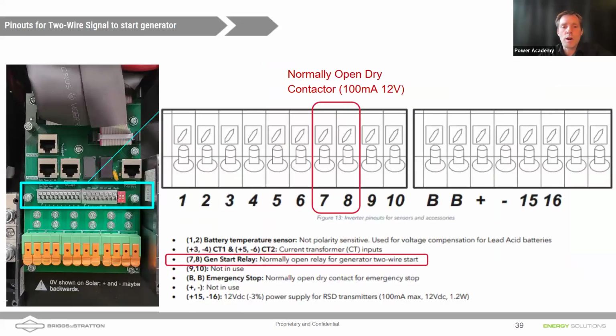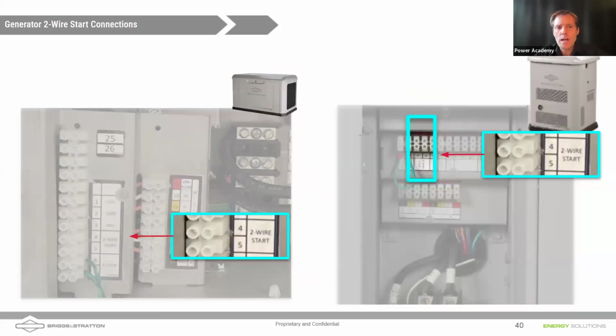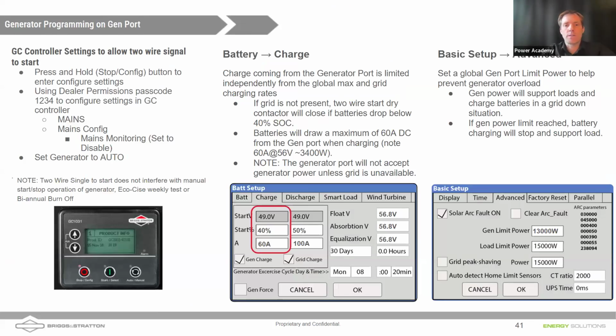You also want to make sure you wire that two-wire signal to start if you have an automatically starting generator. On our generators, that's pins 4 and 5 on our control boards. And that's a normally open dry contactor. So in a Briggs & Stratton generator, this is the sequence that you would use, including the password, in order to disable auto main sensing and enable two-wire signal to start. So this keeps the generator from monitoring and starting up as soon as the grid goes down, right? It allows the inverter to control the start-stop through two-wire.